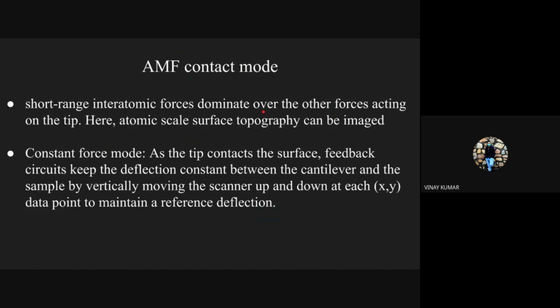So AFM contact mode works on short-range inter-atomic forces, which dominate over the other forces acting on the tip, which we have already discussed. This is used for atomic-scale surface topography imaging. In contact mode, as the tip contacts the surface, the feedback circuit keeps the deflection of the cantilever constant by vertically moving the scanner up and down to maintain the reference deflection.